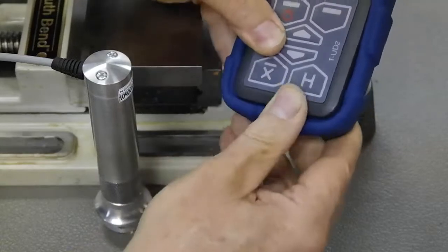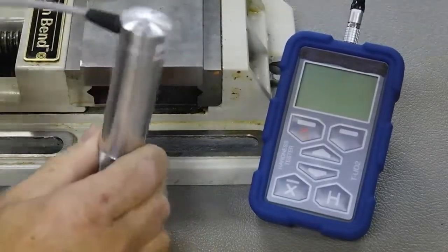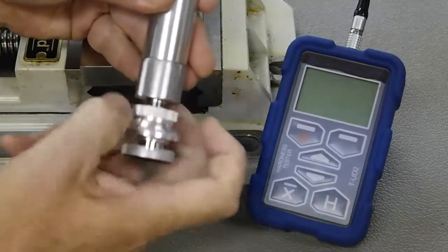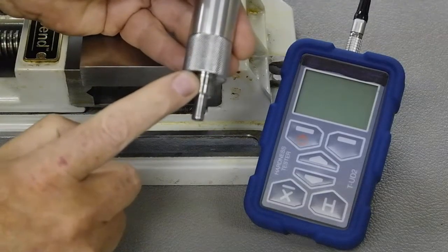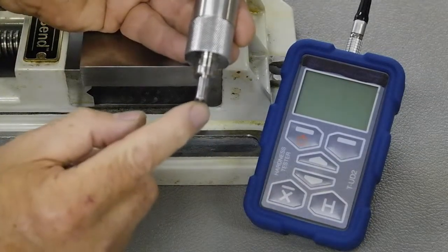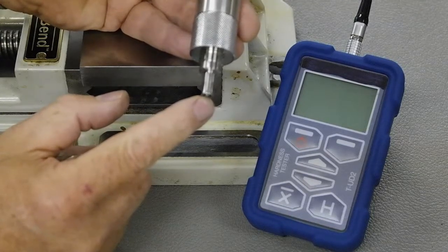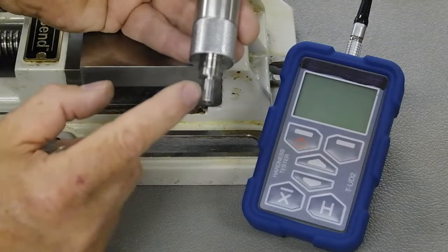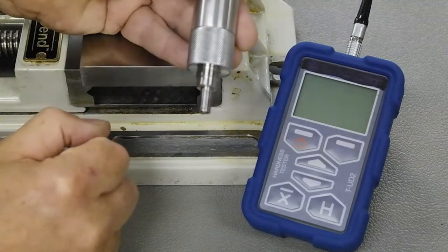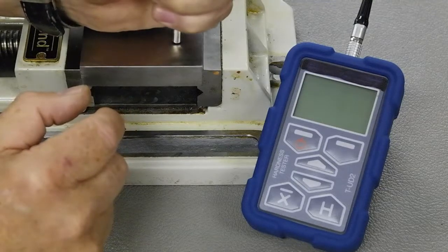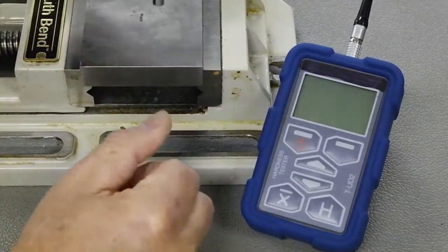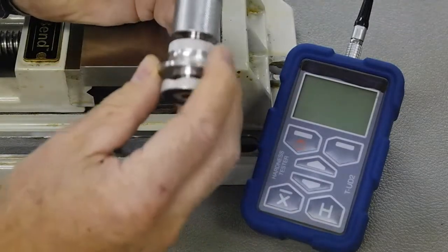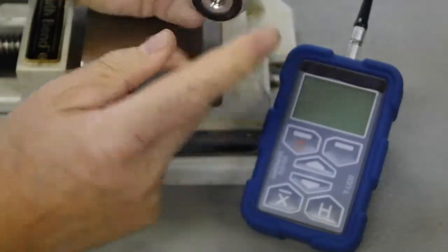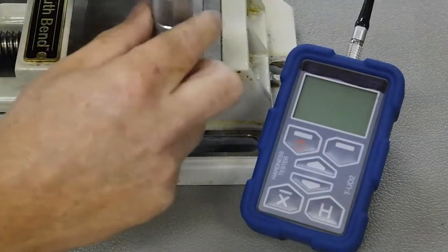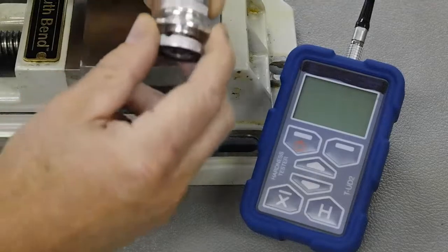So another thing with the tester is that we include the foot. And this foot here can be screwed off. You can see, so we go back to the probe itself, its shroud. Here is the little Vickers diamond tip, and this is on a very high frequency vibrating rod that's inside the device, of course. So you can actually freehand it right like this, always with two hands so you keep it stable. Or we include the foot, and the foot here is flat on the bottom, as you can see, so very easy for doing quick tests on flat parts.